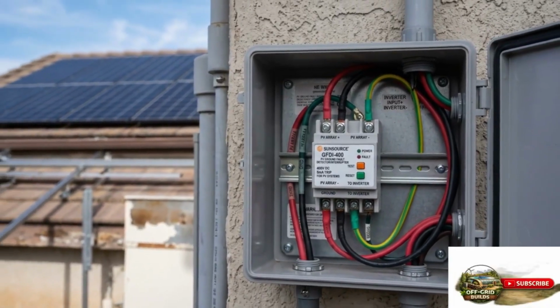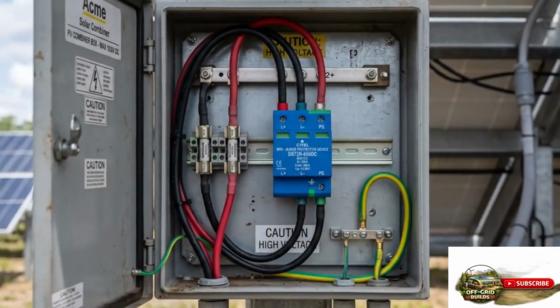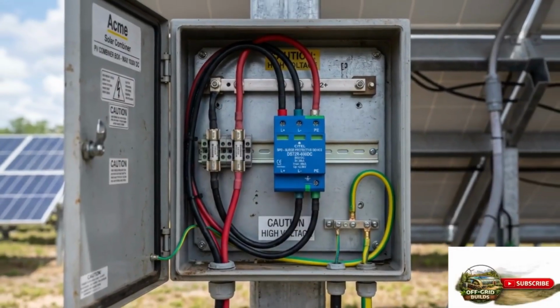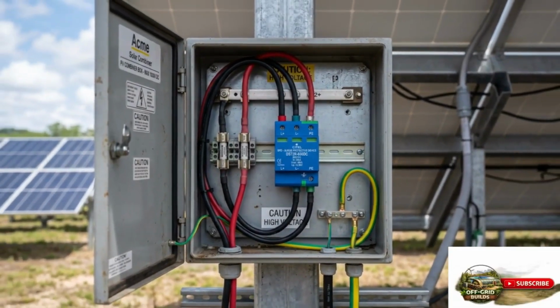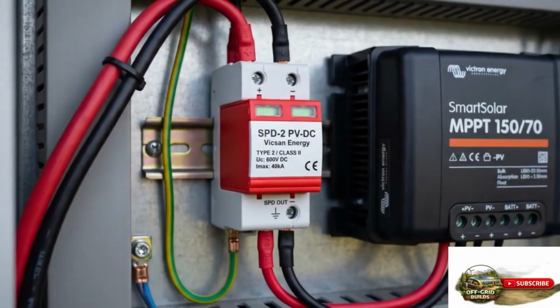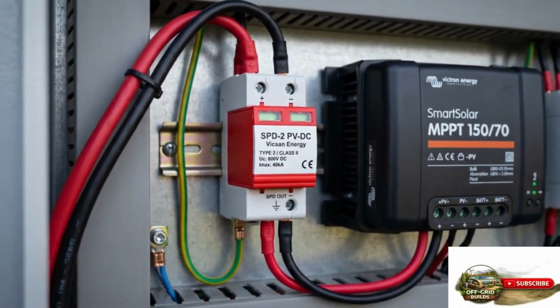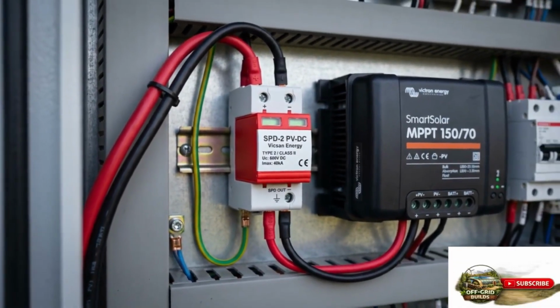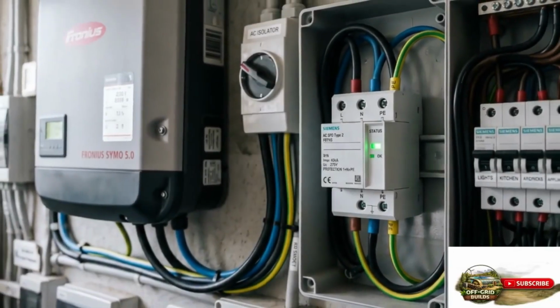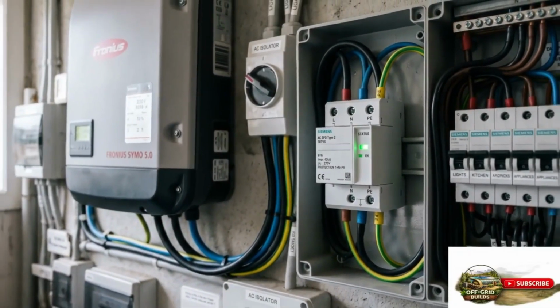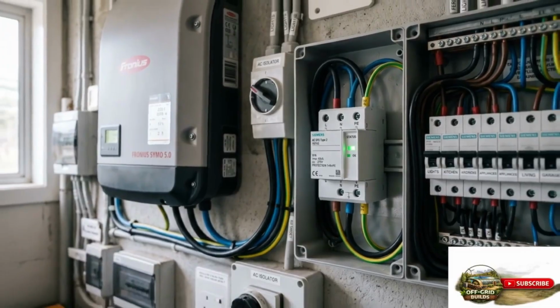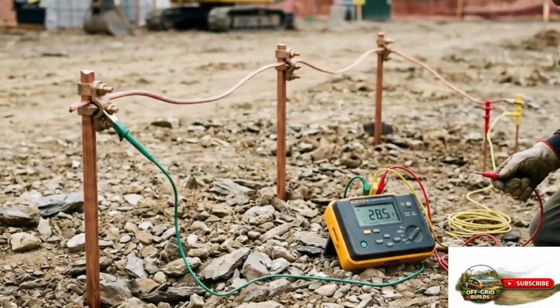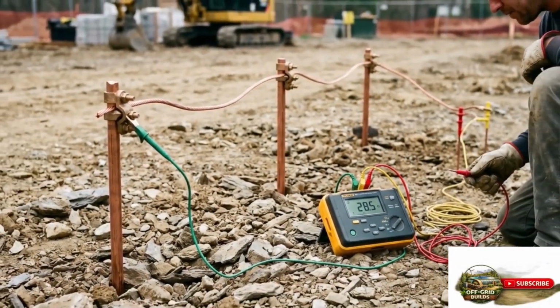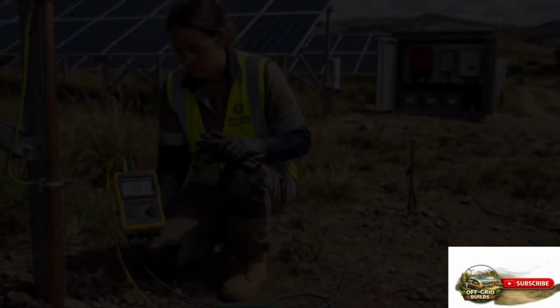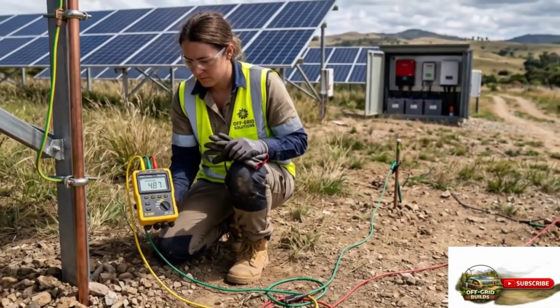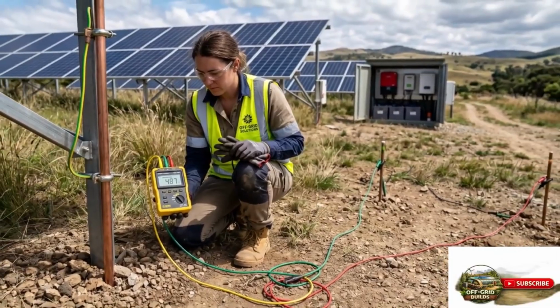The system grounding electrode typically consists of one or more ground rods driven 8 feet into the earth near the electrical service entrance of the system, connected to the main grounding point with 6-gauge or larger copper conductor. For a large off-grid system in an area with poor soil conductivity, multiple ground rods may be required to achieve an acceptable grounding resistance.